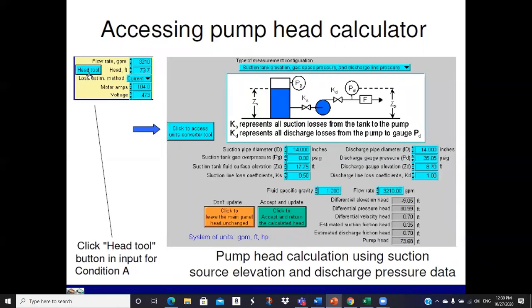And there's two configurations of it. This is the one that shows the suction tank with the elevation on the suction side of the pump, loss coefficients for any fittings or anything that's in here. You've got an entrance loss for sure. That's a square edged entrance going into the pump. And then some discharge loss coefficients. We can have an overpressure, or it can be zero, atmospheric, elevation. Discharge gauge, you almost always have a discharge gauge, flow meter, and elevation of the flow meter off of your datum. And so this is just putting numbers in, and it calculates a pump head for you.